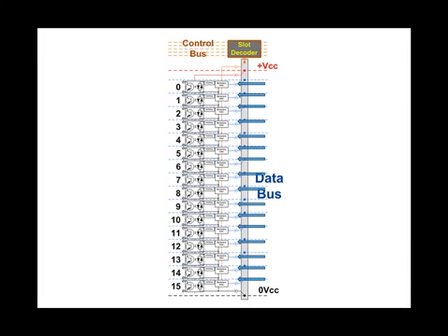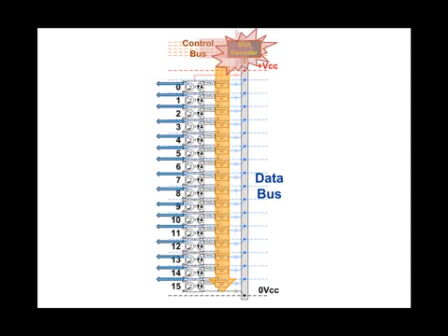Each slot has a decoder that is unique to that slot, in that it responds to a bit pattern sent from the processor on the control bus that corresponds to that slot and that slot alone. When this happens, the output of the slot decoder activates all 16 gate circuits, and the state of all 16 backplane conductors of the data bus are felt at the holding circuit of all 16 output circuits. That is the sequence of an output signal from the processor.